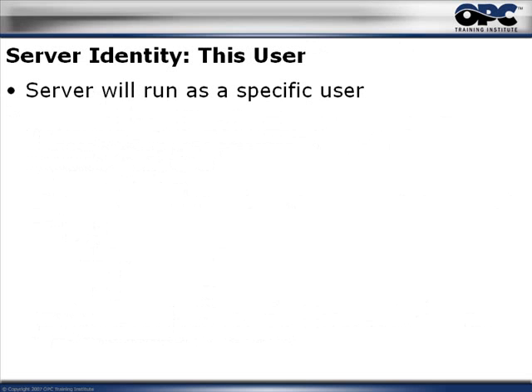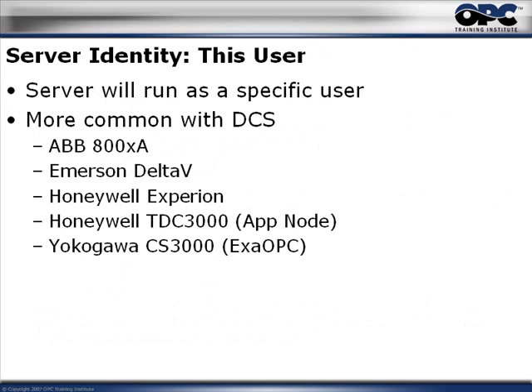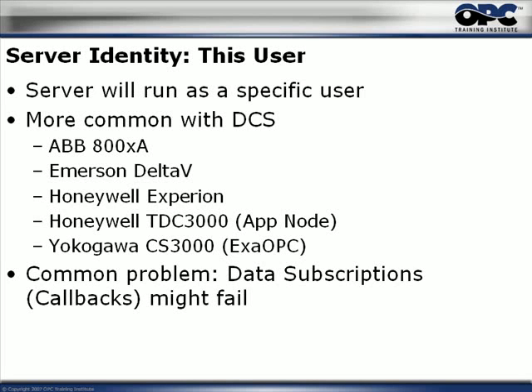The next server identity is 'this user,' and we often see it recommended by DCS vendors. In their case, the OPC server has to run as a very specific user because their data sources are tightly coupled to it — those data sources will only provide data to a specific user. If that user isn't the one requesting data, they refuse to provide it. So the server must run with a specific username and password. This isn't inherently bad; it's just how their security model works.